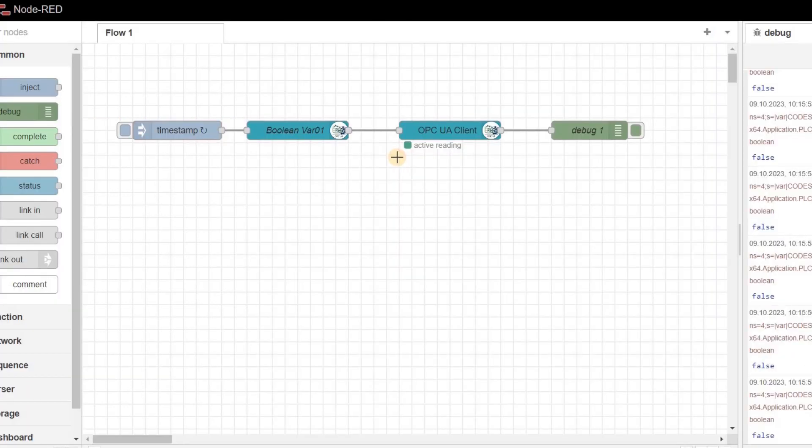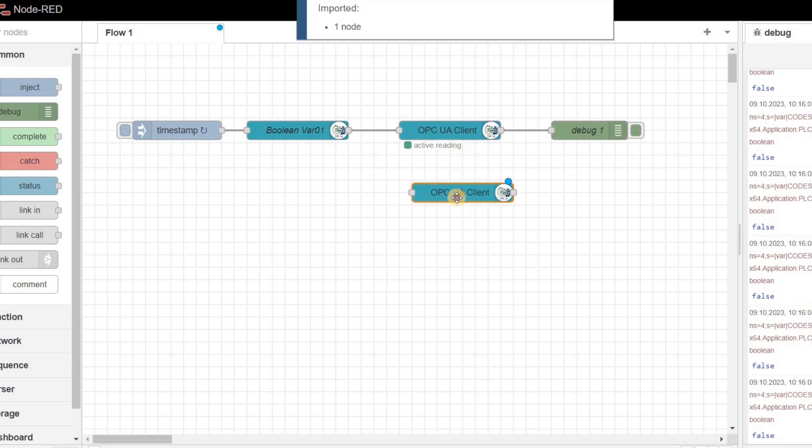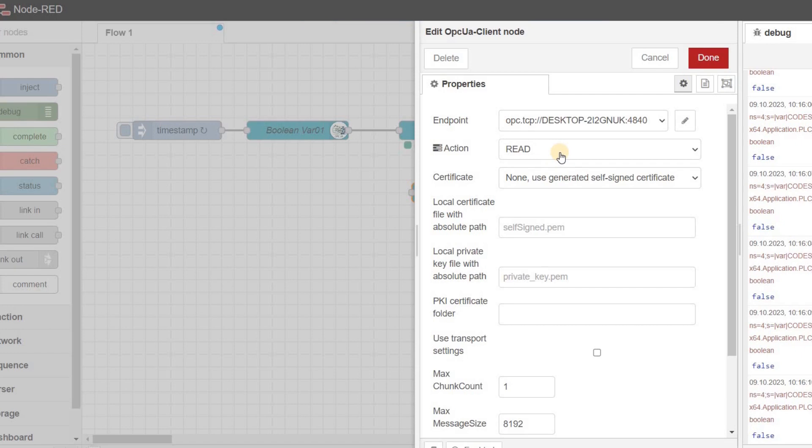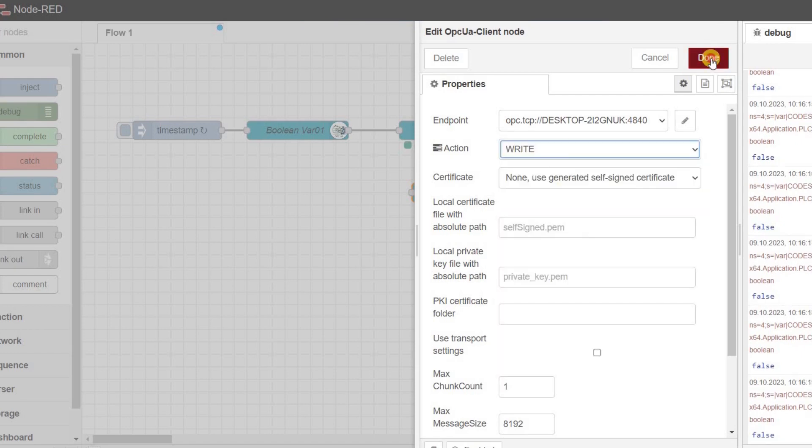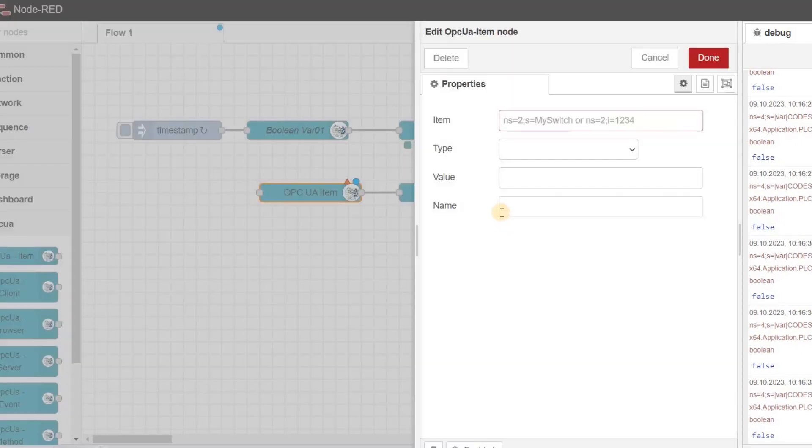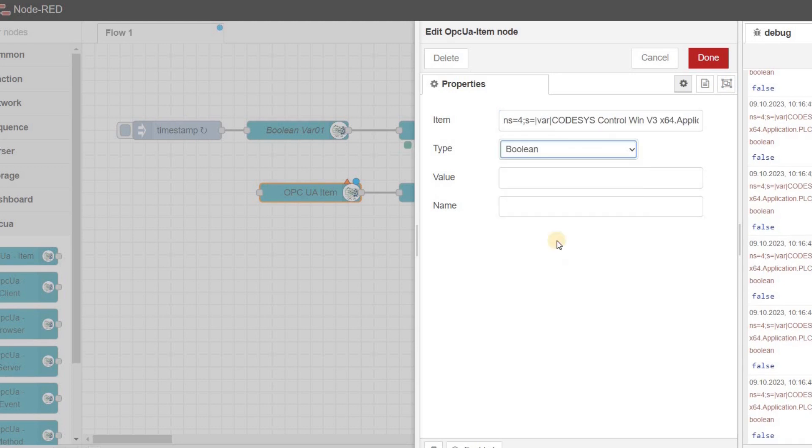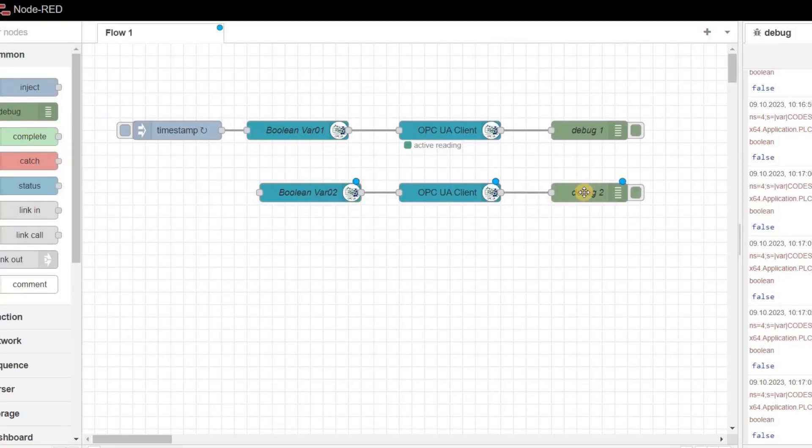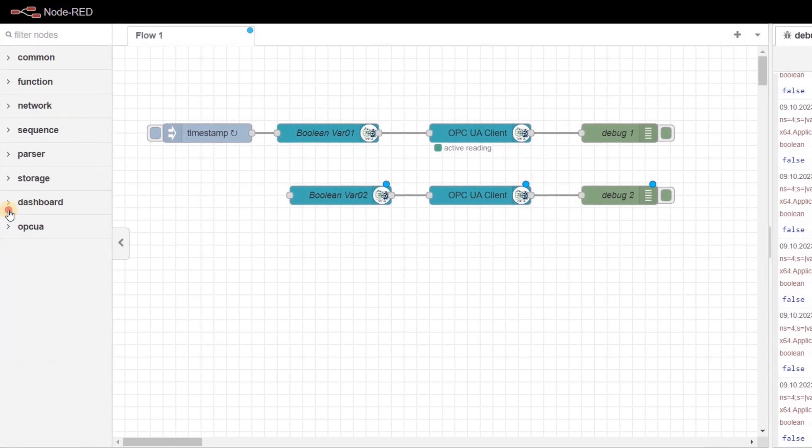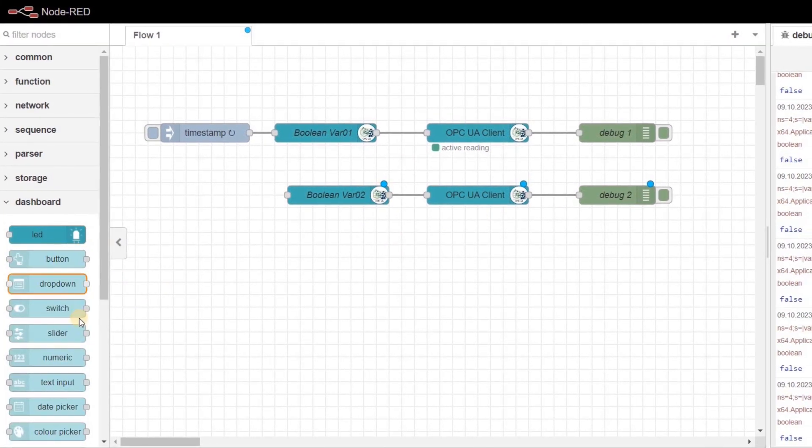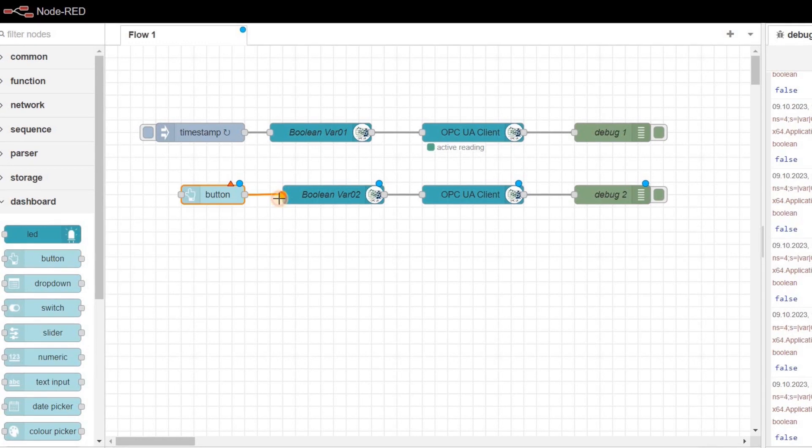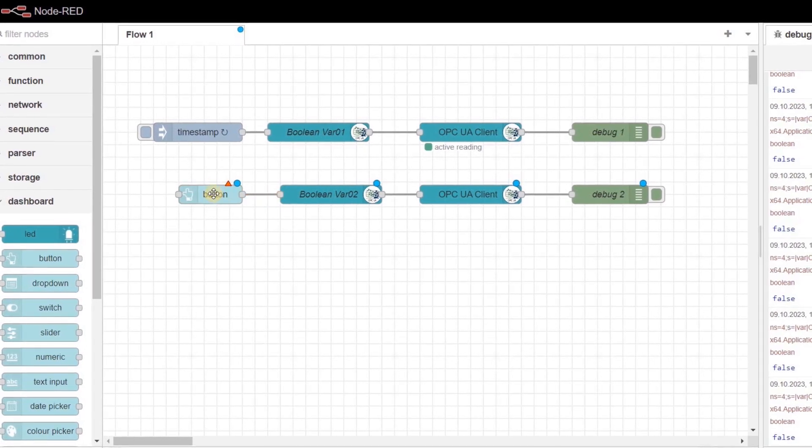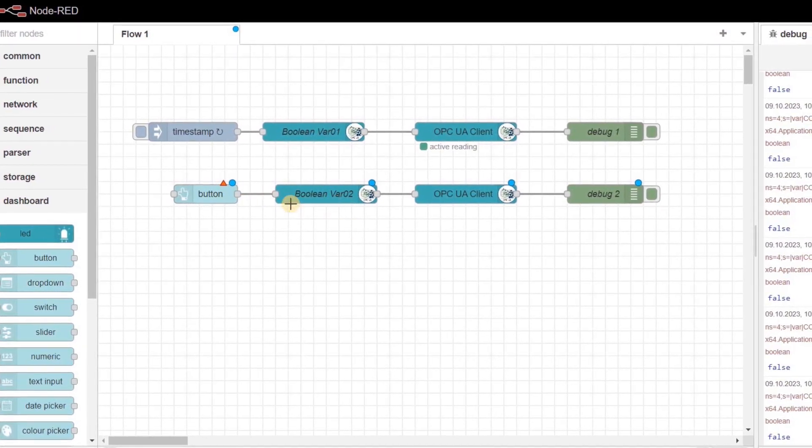As the next action, let's write a value to a variable. I make a copy of the OPC UA client node and change action to write. For the OPC UA item, I am using bVar02 with the name of booleanVar02. We can place a debug node as well and to determine the value to be written, I am going to use a button node and connect it to the OPC UA item.